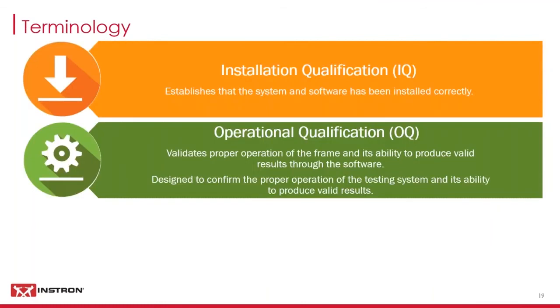Before we go any further, we have yet another acronym, IQOQ. IQ, or Installation Qualification, establishes that the system and software have been installed correctly. OQ, or Operational Qualification, validates proper operation of the frame and its ability to produce valid results through the software. The OQ, in combination with transducer verifications, is designed to confirm the proper operation of the testing system and its ability to produce valid results.